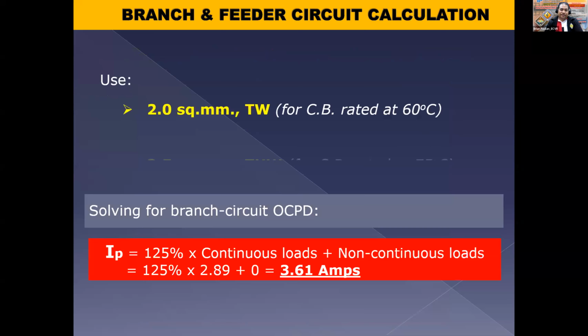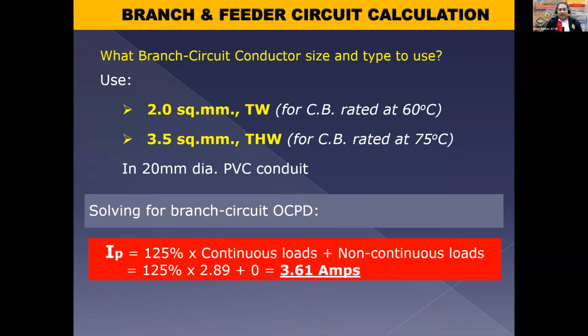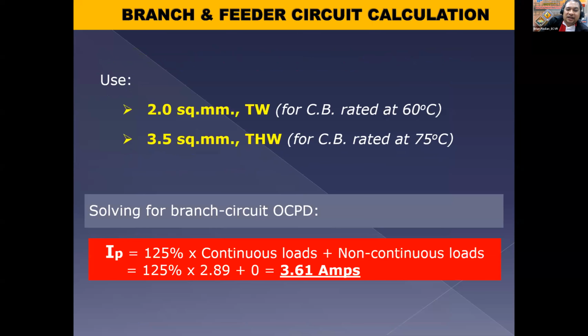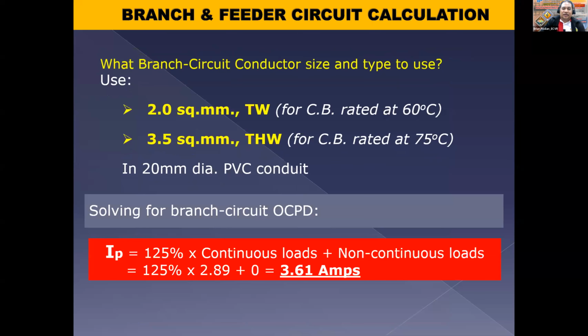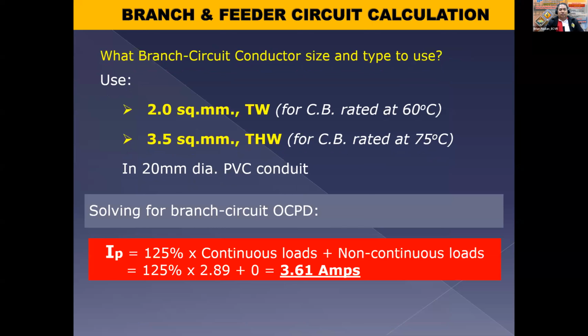Okay? So for example, ito, no? Yung kuha natin kanina, so if we're going to use 2 mm squared because ito yung it can already handle the load, no? So just keep in mind for temperature matching purposes, use circuit breaker rated at 60 degrees or higher.